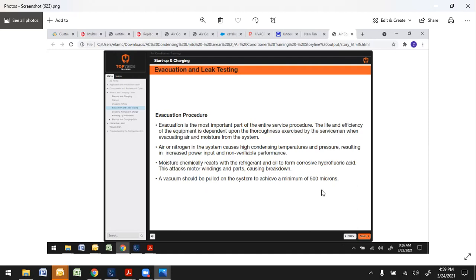They don't really go into the triple evacuation here. With these new vacuum systems, if you have a good pump, clean oil, the large vacuum hoses and the right setup, you can suck it down to 500 microns quickly. The problem is you're drawing it down so fast that you can still end up with moisture in the system even though you're at 500 microns.